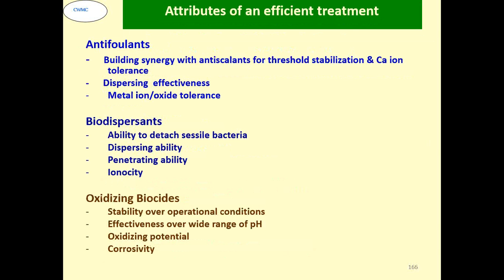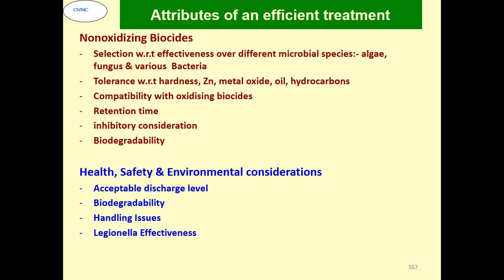Antifoulants are used for building synergy with antiscalants for threshold stabilization and calcium ion tolerance. Dispersing effectiveness, metal ion oxide tolerance. And for biodispersants, ability to detach sessile bacteria, dispersing ability, penetrating ability, and ionocity. Oxidizing biocides are used for stability over operational conditions, effectiveness over a wide range of pH, oxidizing potential, corrosivity. Non-oxidizing biocides are selected for effectiveness over different microbial species, algae, fungus, and various bacteria. Tolerance with respect to hardness, zinc, metal oxide, oil, hydrocarbon, etc. Compatibility with oxidizing biocides has to be seen.